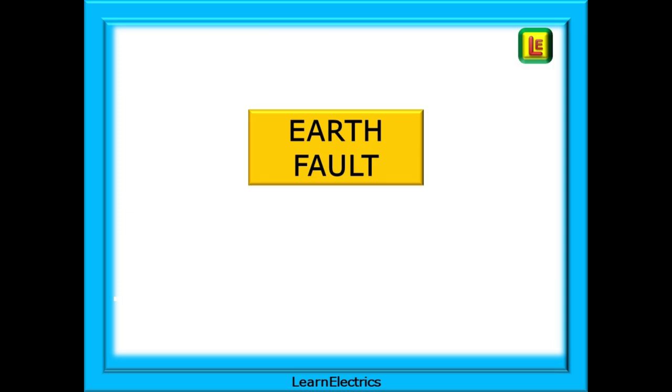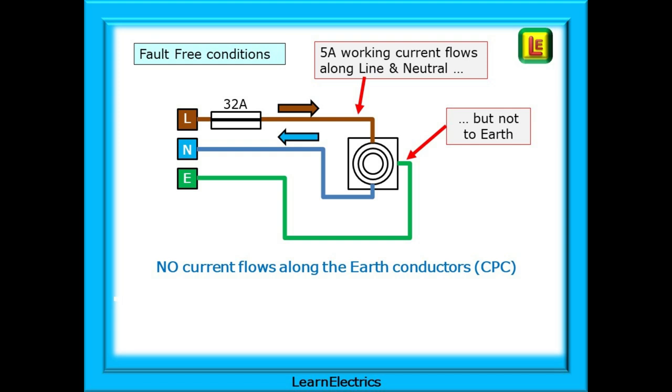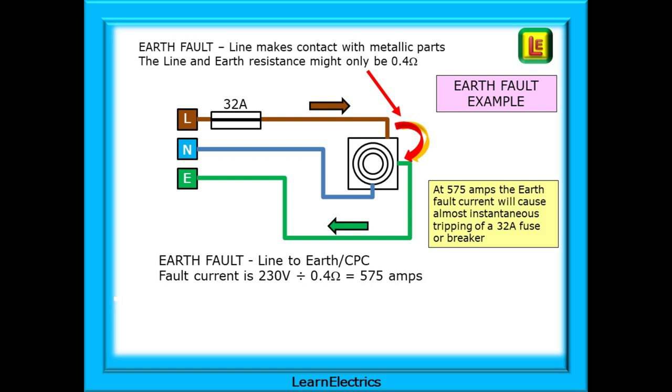The third type of overcurrent is the earth fault. If we begin with a fault-free scenario and use the same cooker ring again, we can see that the 5 amps of working current flows along the line and neutral wires but nothing along the earth conductor. The earth or CPC is connected to the metallic casing of the cooker. Now let's have an earth fault. Something happens and the line conductor makes contact with the metallic parts of the cooker. This effectively bypasses the cooker ring and the cooker ring resistance. Earth fault current flows along the line conductor through the metallic casing to the earth or CPC wire that is attached to the cooker. And this will be a low resistance path. If we say that the total resistance of the line and earth path is only 0.4 ohms, how much earth fault current will flow and will it cause the 32 amp breaker to trip? Using Ohm's law again, 230 volts divided by 0.4 ohms is 575 amps.